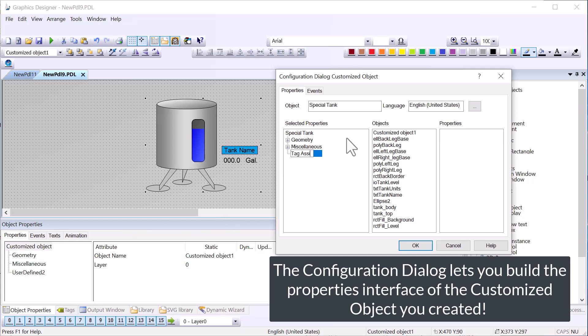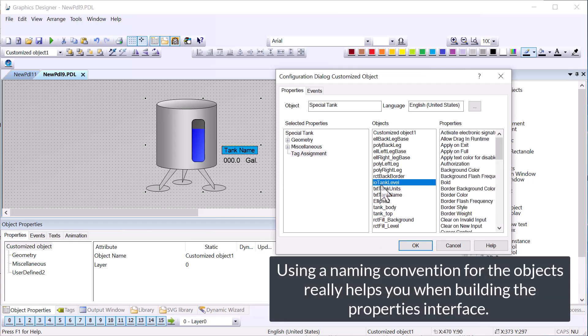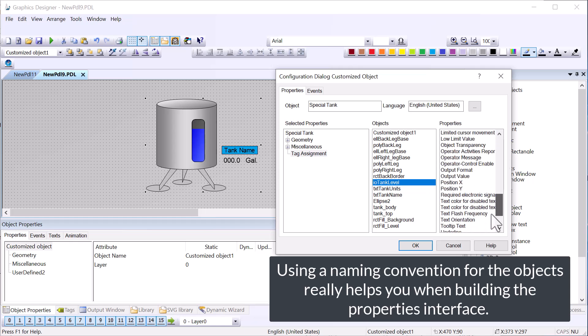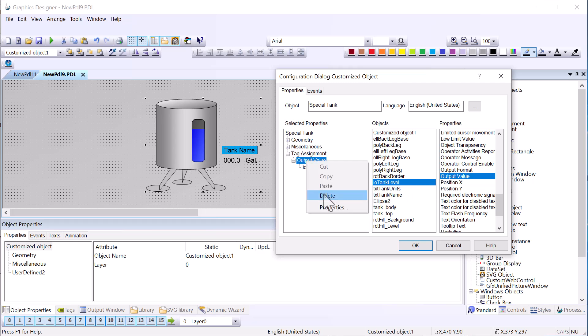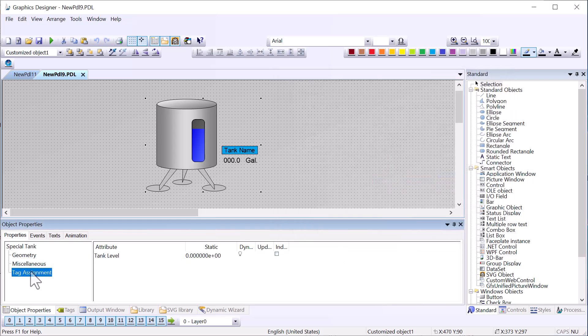Let's call this topic 'Tag Assignment' and we'll start with the IO field. I can pick the IO field out because I named it appropriately using Hungarian notation — 'io' means it's an IO field, 'tank level' tells us what it does. That's a big thing I teach in my classes. Now we'll use the Output Value — this is where you assign tags to an IO field — and I'm just going to drop it right on top of Tag Assignment and rename this property 'Tank Level' and click OK.